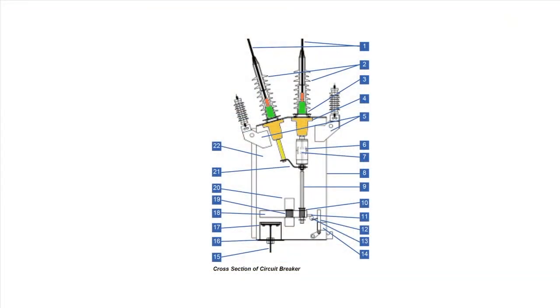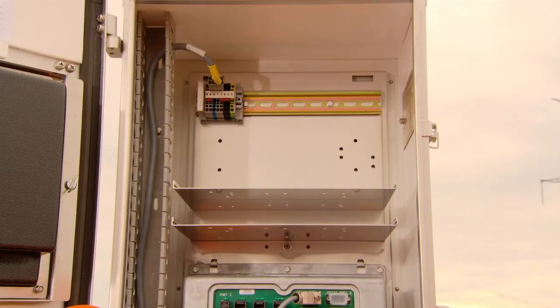The ADVC reads and displays the switchgear-related information that is stored in the switch to which it is connected. Therefore, if the ADVC is moved to another switch, it reads the data from that switch. The ADVC customer compartment provides room for other equipment. Standard communications cables can be used for connection to the communications ports on the CAPE, and power is readily accessible from the power terminal block located on the customer compartment. The compact cubicle has 1 customer compartment, while the ultra cubicle has 2.